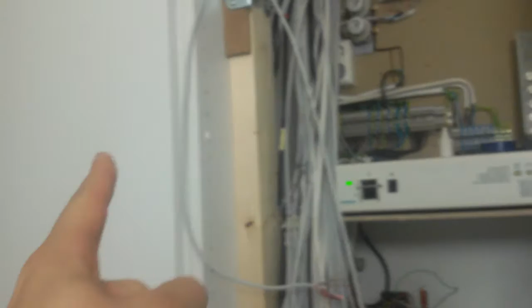There are some smoke detectors on the top, and one in there as well. That will trigger a relay on this board, which will come here, and that one, and that will shut down the main contactor, which is in that board over here, and it will shut that down. So if one of the inverters actually burns, it doesn't matter - it shuts down the main if it's the inverter causing the problem, and it actually shuts down the 12 volt line as well.